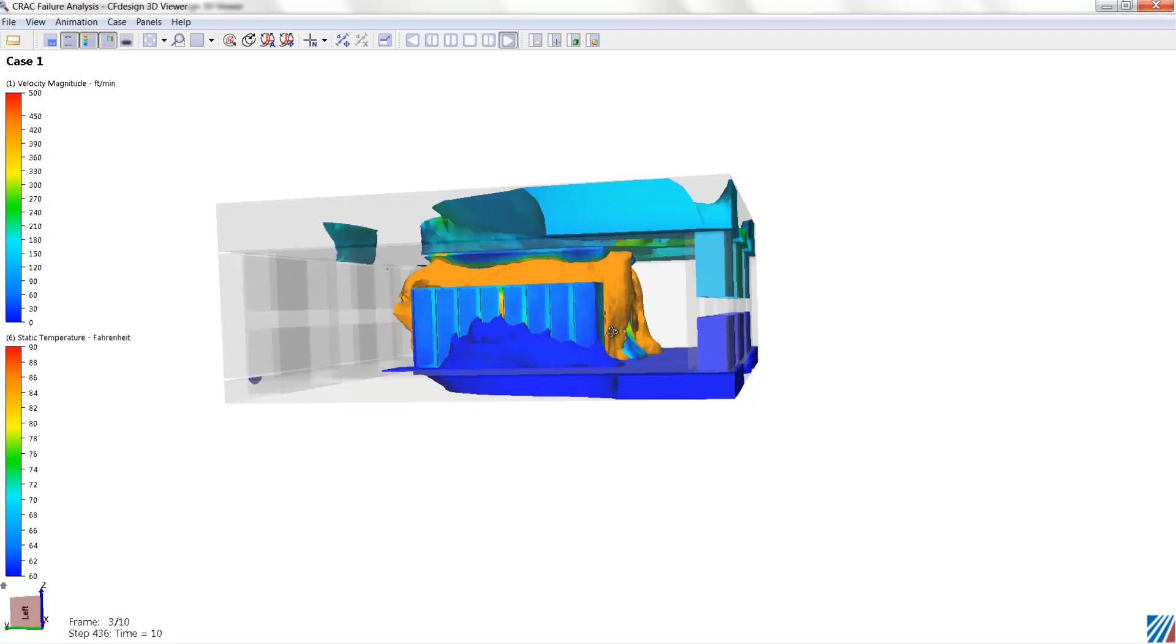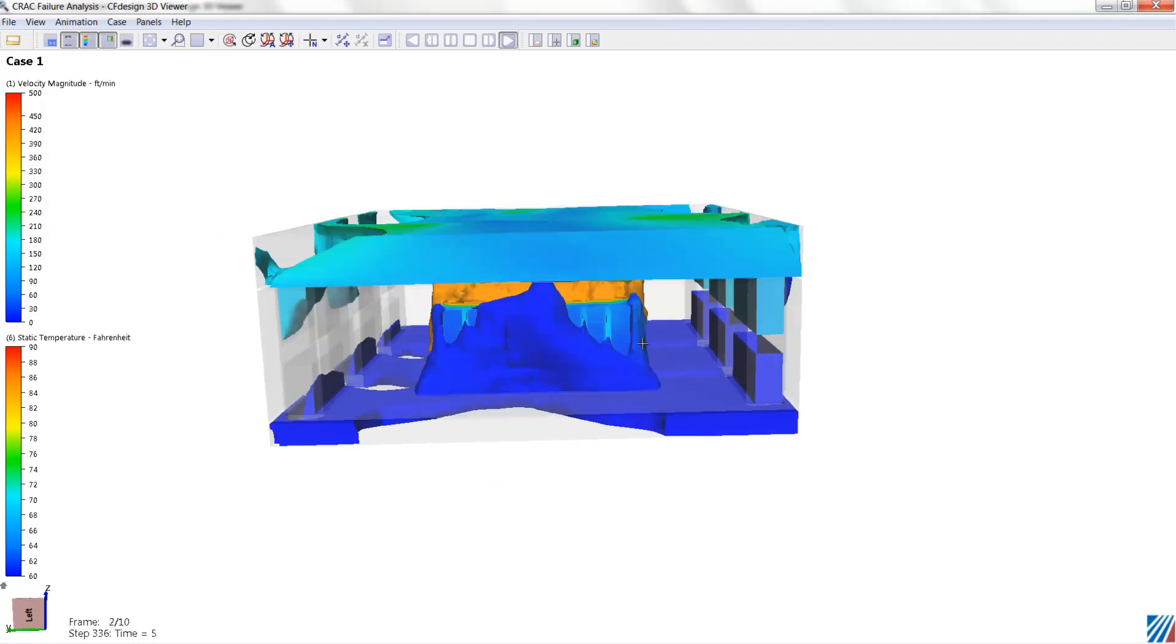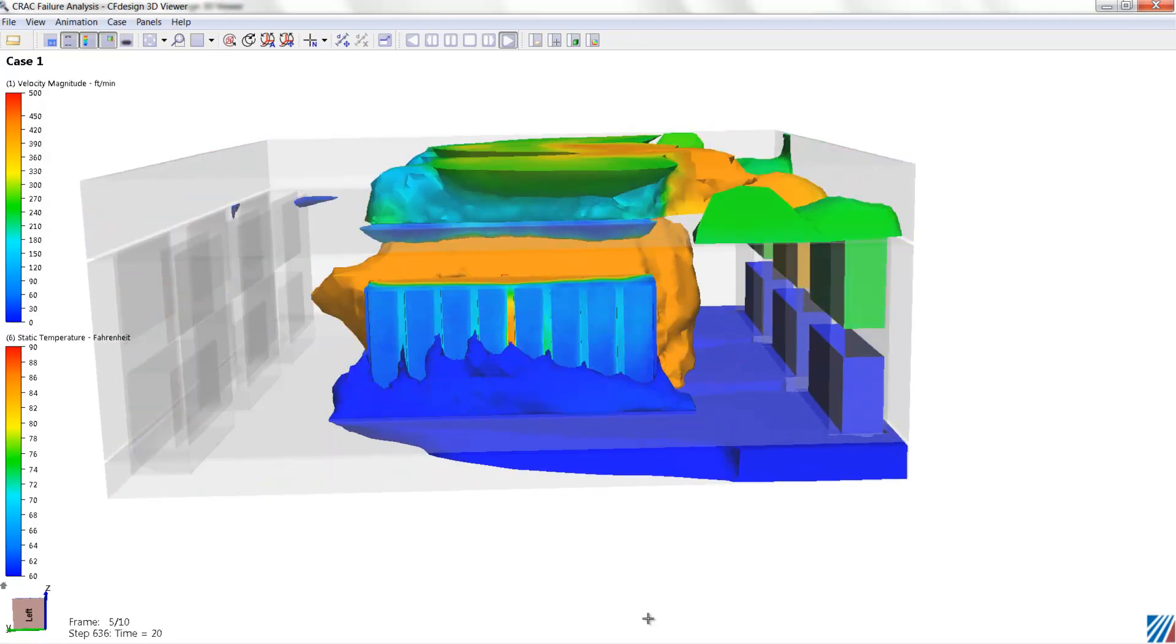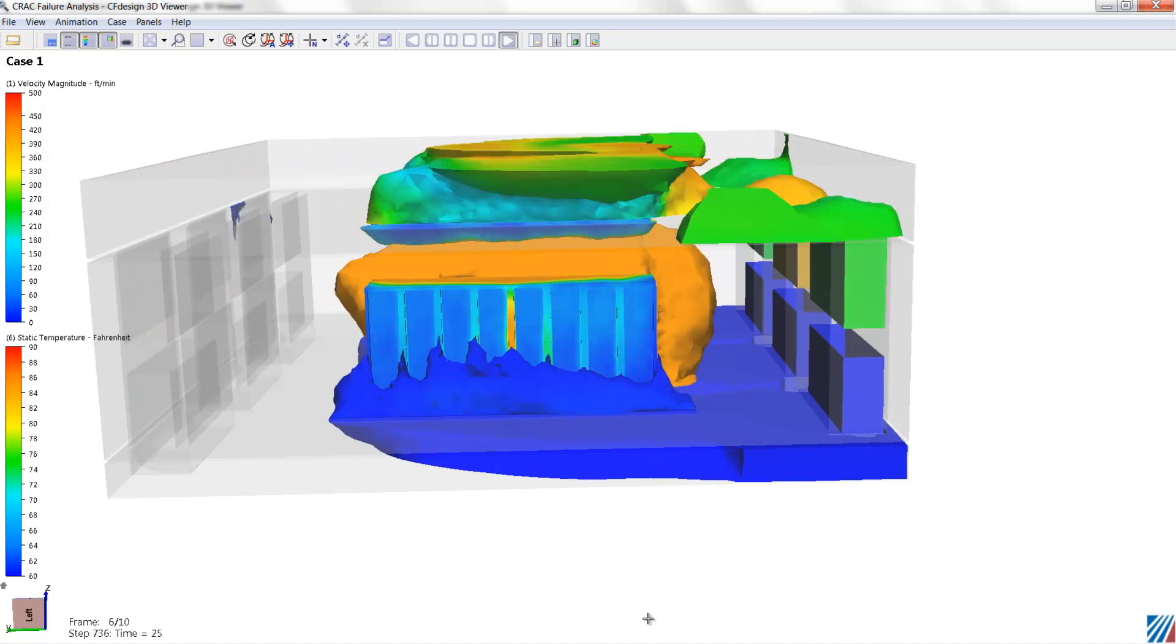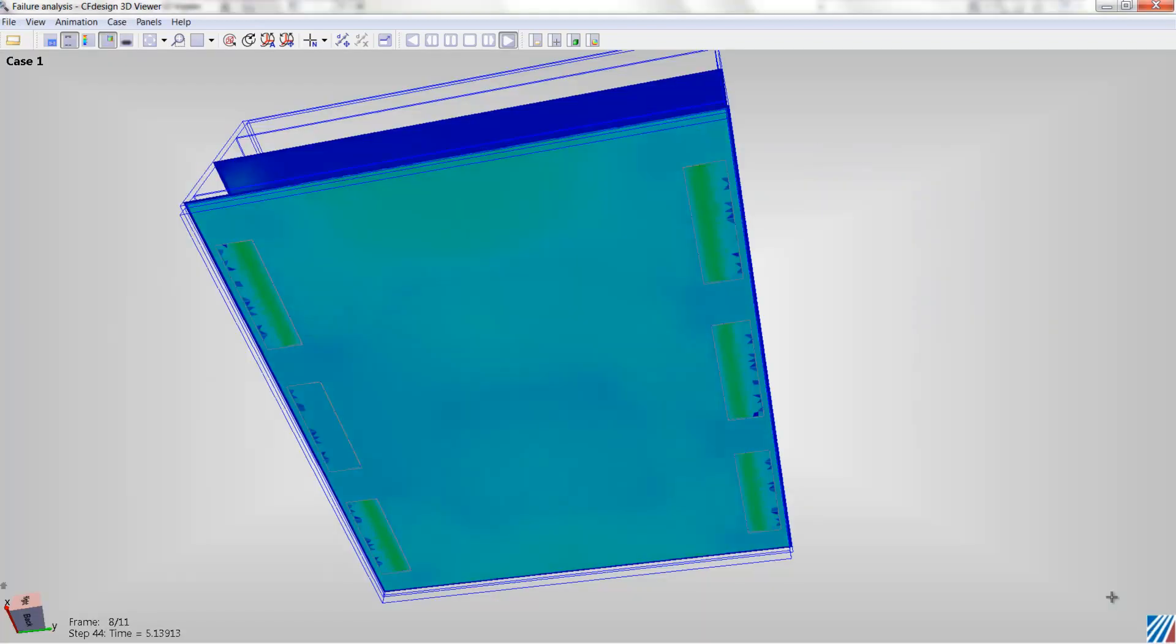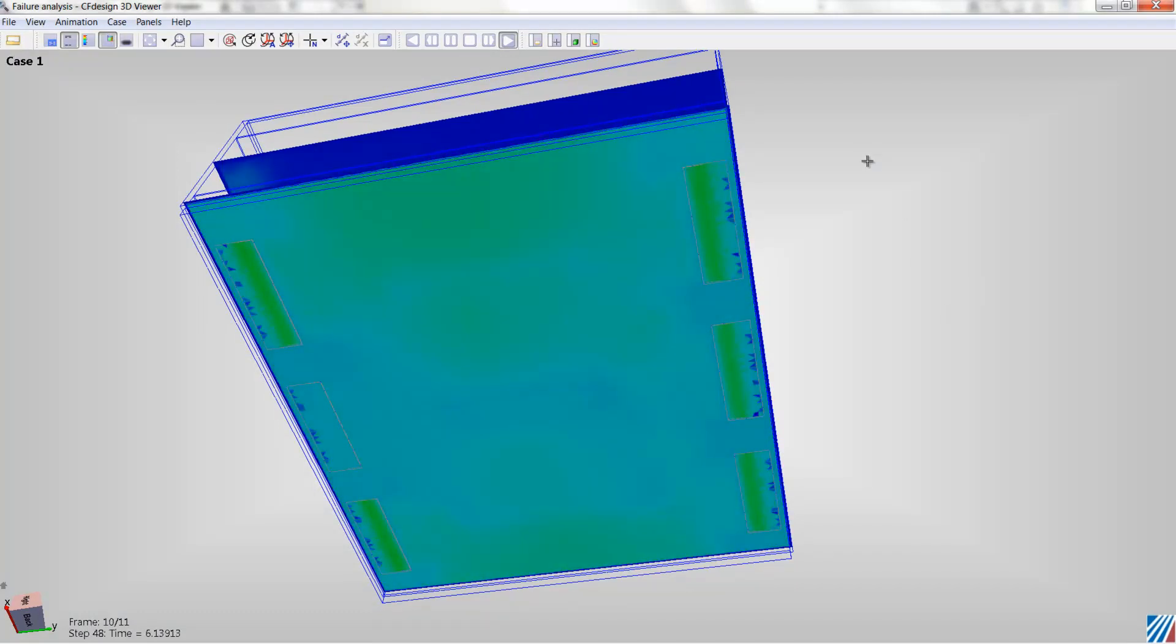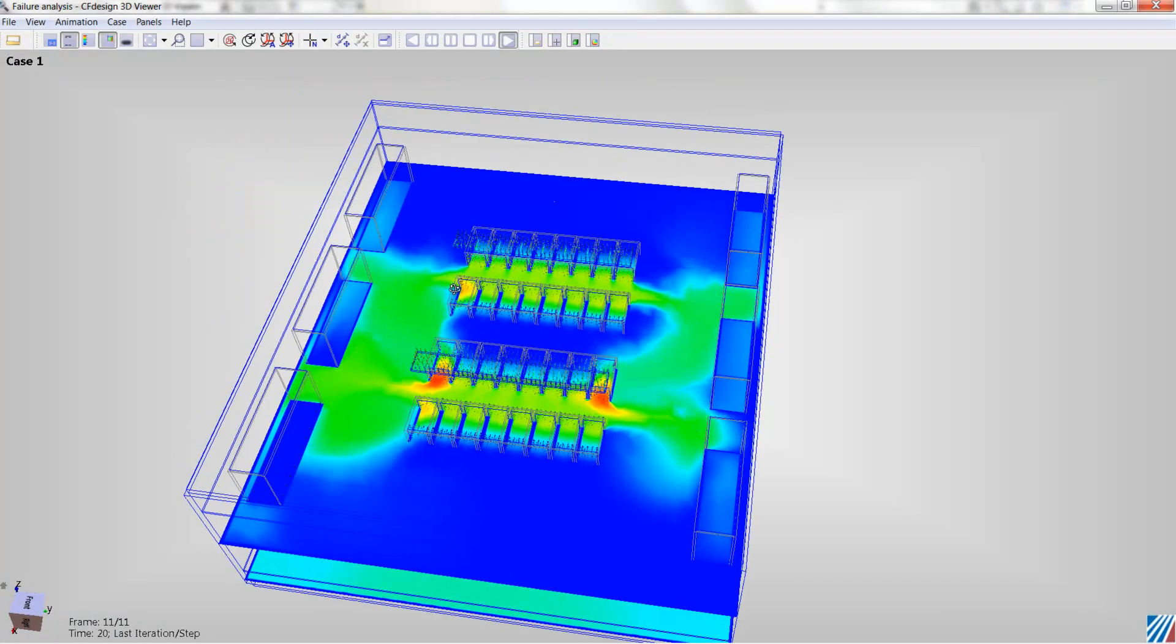And then, the ultimate analysis to investigate here is a transient failure scenario where we actually shut down one or more of the CRAC units and track the performance of the room over time. So these analyses are commonly requested by owners now as they attempt to reduce redundancy, save more energy, and fully understand failure scenarios.